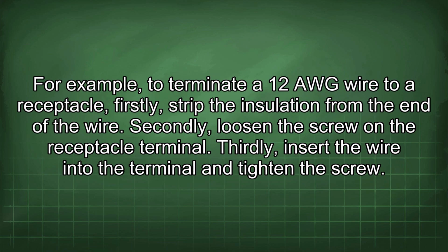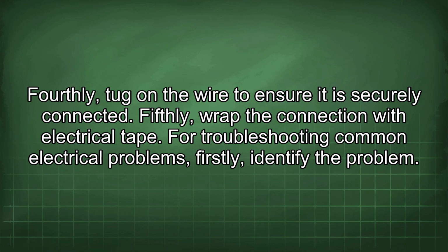For example, to terminate a 12 AWG wire to a receptacle, firstly, strip the insulation from the end of the wire. Secondly, loosen the screw on the receptacle terminal. Thirdly, insert the wire into the terminal and tighten the screw. Fourthly, tug on the wire to ensure it is securely connected. Fifthly, wrap the connection with electrical tape.